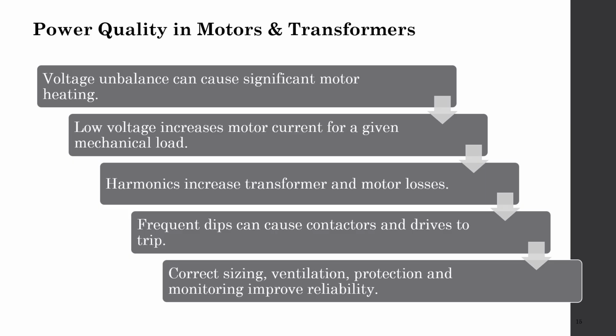Power quality in motors and transformers. Voltage unbalance can cause significant motor heating. Low voltage increases motor current for a given mechanical load. Harmonics increase transformer and motor losses. Frequent dips can cause contactors and drives to trip. Correct sizing, ventilation, protection, and monitoring improve reliability.